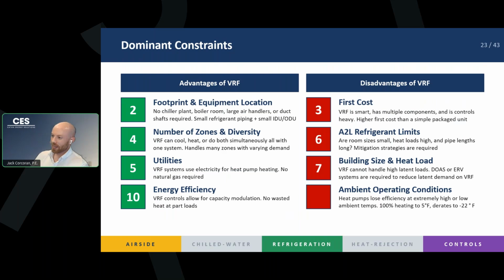It actually works the same in reverse, right? So when we're heating, we have to think about what our ambient temperature is outside. So can we get our refrigerant temperature to be 0 degrees or less than 0 degrees on a low day, right? We want to be able to heat even though it's really, really, really cold outside. Otherwise, we don't have any heat in the winter, and that's a huge problem. So nowadays, almost every VRF system is going to be able to provide 100% heating down to 5-10 degrees Fahrenheit. And it's slowly going to derate down to -22. And, once we reach -22, manipulating our pressures is no longer going to work. We have to figure out a different way to heat. So if you know you're going to encounter days that are well below 5 degrees or well above 100 degrees, maybe you got to think about how we can get a different form of heating or cooling.